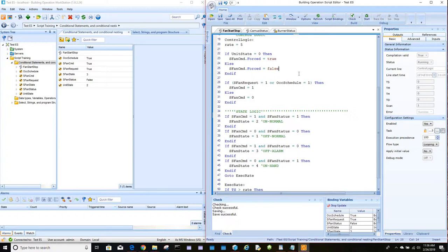There are a number of other attributes. We have an overridden attribute, which would only be good if we had an ASP or B3 to work with. I believe this actually only works for ASPs. So if we had an ASP to work with, we could use the overridden binding attribute, which will just give you status of the physical toggle or override potentiometer for analog and digital outputs on an ASP device, or any kind of AS device.